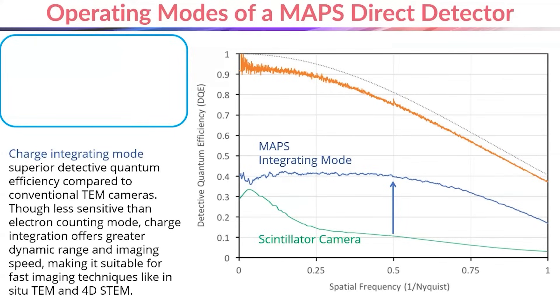However, the charge each electron deposits in a MAPS sensor is variable, and this creates a source of noise called Landau noise. To overcome Landau noise, microscopists developed a second mode of operation for MAPS detectors: electron counting.